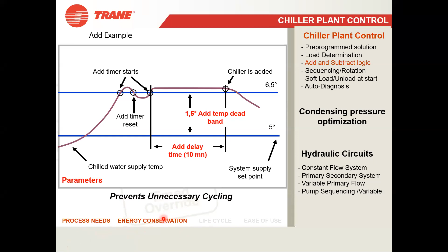So what will be happening now? You can see the chilled water delta temperature. Now in the office there are fewer people, so definitely you will feel more cold. This is a normal phenomenon, right? You feel more cold in the evening or in the afternoon when fewer people are there. Then this chilled water delta T will be decreasing, and when it reaches the dead band, wherever I have set it, here I have set it at 2.8 degrees, it will again start the timer.